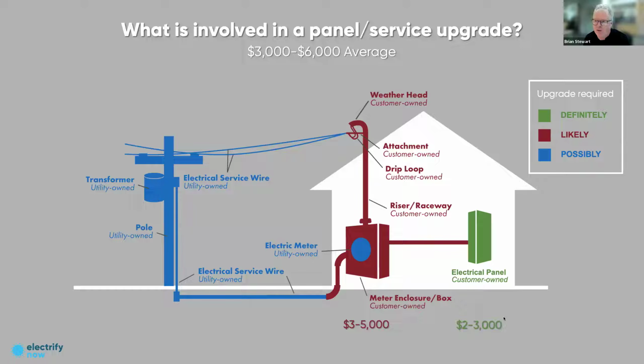But if you need a service upgrade, meaning more amps to the panel, that starts to trigger other potential things. If you've got a 100 amp panel right now and want to go to 200 amps, it's very likely you don't have enough service to your home to drive 200 amps. So you're going to need a new meter enclosure box, probably a bigger, fatter wire from the meter to the overhead service lines, and the utility may or may not need to make changes on their end to ensure 200 amps is coming into those wires to your panel.